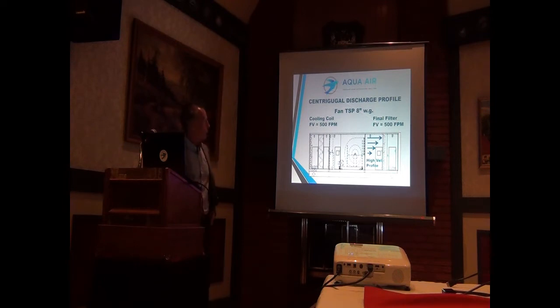One thing in this design that is important to talk about, this distance here makes the footprint of these units a lot larger than the other fans that we'll talk about. And why is that? You have to keep this space to help the air be less turbulent or laminar flow. In some cases you can have, with this top filter, if this was too close to the outlet, you can damage that top filter, or it might even blow it out.